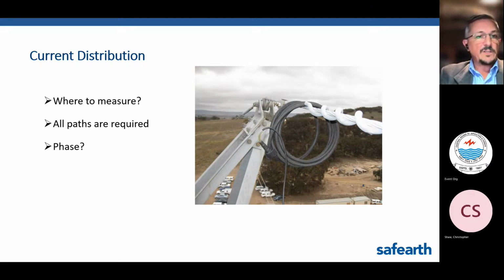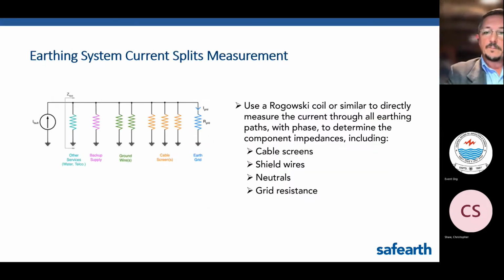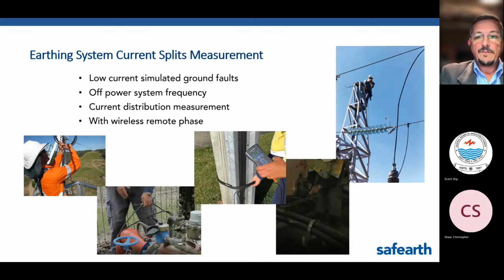So if you want to measure the current to determine those things, you've got to ask, where will I measure it? And do I need phase to measure it? Using, again, a frequency tunable meter, and now with a Rogowski coil, which is an air cored open-ended CT, which can be wrapped around conductive structures, the current through any of those conductive structures can be directly measured. This allows determination of coupling factors for lines and cables and input impedances for neutrals and any other conductive element. Even current flowing through fences and water pipes can be measured.